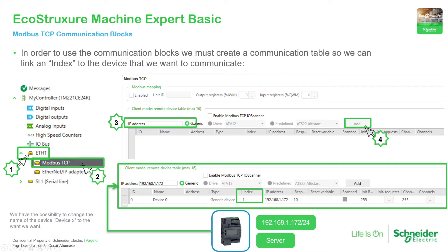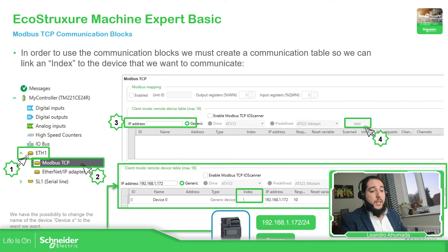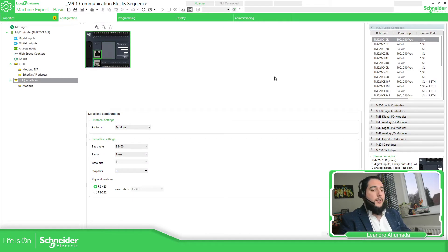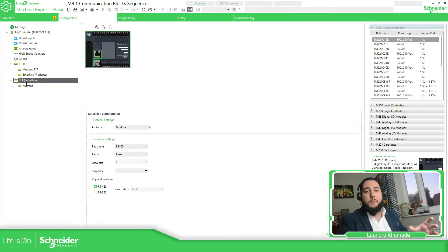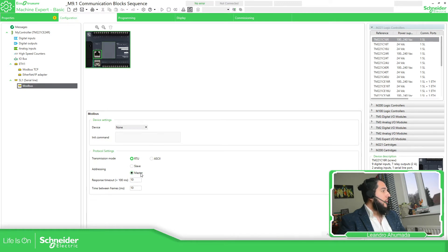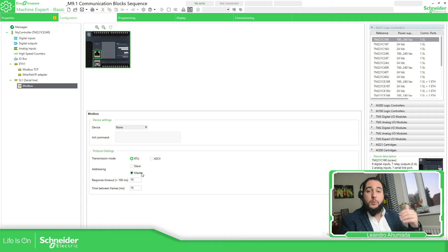There is something different compared with the communication blocks in Modbus serial. In Modbus TCP, we need to create a table, and in that table we need to specify an index for each device that is going to be linked to the function block we're going to use. Going back to the application done for Modbus serial, you needed to define the PLC as a master in the communication with all the Modbus parameters. The M221 was the master used to connect with the M172.